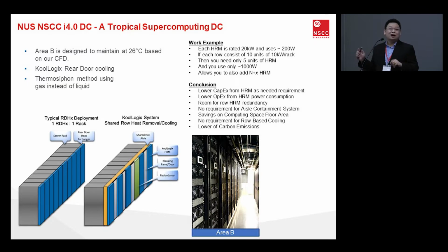Hence the positive pressure. Of course, in the event that there's a human in the room, having an FCU gives airflow, so at least the human inside can survive. The room is designed to maintain 26 degrees. That's slightly higher than what the Singapore government has proposed, 25 degrees. We're pushing it to 26 because we did our calculation, and 26 is the best for the system. Why we are saying that is because of the KoolLogix's rear door cooling. The KoolLogix's rear door cooling itself acts as a cooling system for the whole room. Later on, I'll explain why.